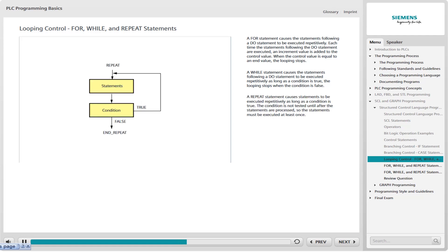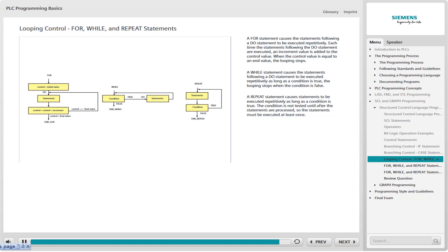A REPEAT statement causes the statements following the REPEAT statement to be executed repetitively as long as the condition is true. The condition is not tested until after the statements following the REPEAT statement are processed, which means these statements must be executed at least once. If the condition is true, the looping continues until the condition is false. An END_REPEAT statement completes this part of the program. REPEAT loops can also be nested within a REPEAT loop. These control statements provide useful loop control options, but there are additional options.